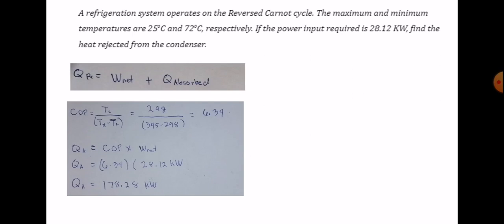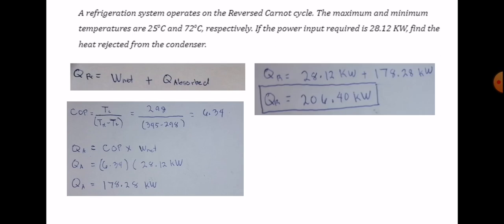COP times the power input. Our power input is 28.12 kilowatts and our COP is 6.34. Multiplying these gives us the absorbed heat: 178.28 kilowatts.